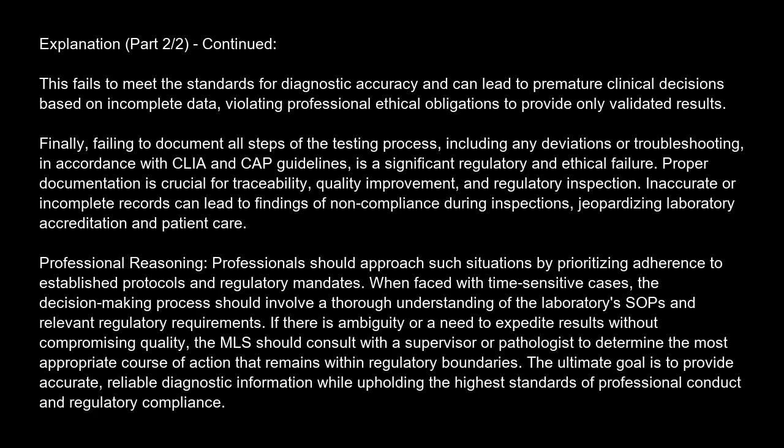Finally, failing to document all steps of the testing process, including any deviations or troubleshooting, in accordance with CLIA and CAP guidelines, is a significant regulatory and ethical failure. Proper documentation is crucial for traceability, quality improvement, and regulatory inspection. Inaccurate or incomplete records can lead to findings of noncompliance during inspections, jeopardizing laboratory accreditation and patient care.